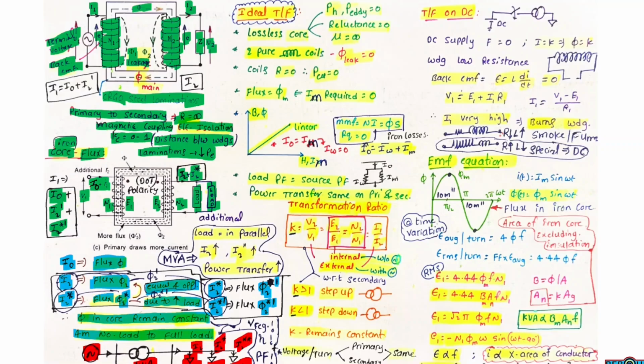So in this way, the additional currents will cause additional fluxes and the corresponding primary currents will cause opposite fluxes. All these fluxes will cancel each other and the final flux remaining in the transformer core is always constant, that is the flux caused by the no load current I0. The flux in the transformer core is not affected by voltage regulation, efficiency and power factor. The flux in the transformer is always independent of all these factors: voltage regulation, efficiency, and power factor.